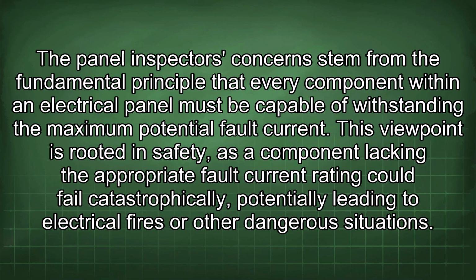The panel inspector's concerns stem from the fundamental principle that every component within an electrical panel must be capable of withstanding the maximum potential fault current. This viewpoint is rooted in safety, as a component lacking the appropriate fault current rating could fail catastrophically, potentially leading to electrical fires or other dangerous situations.